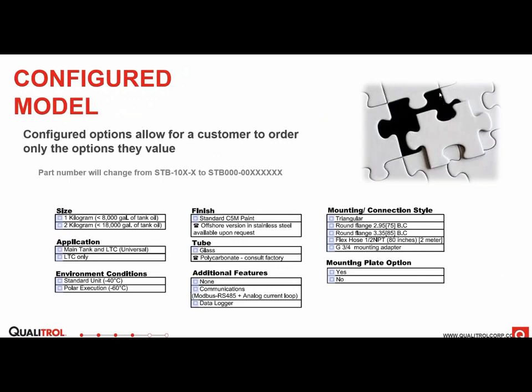Another new benefit of the second generation smart transformer breathers from Qualitrol is that each of them is now a configured model, and it makes it a lot easier to pick and choose the features that you really want for your breather. In the past, we would ship every single one of them with a back mounting plate, and we would go in the field and see that the mounting plate isn't even being used, it's just hanging off the back of the breather. So we decided, why not make that an optional feature?